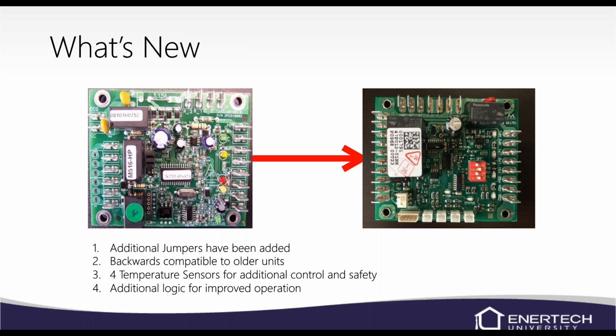So again, some additional jumpers have been added. It is backwards compatible to our older units. And we do have the little Molex connectors. You can see on the right that red dip switch box instead of those jumpers, so it stands out a little bit better. And then you can see the 4 sensor boxes on the bottom of the board. And we've just got some improved logic on the board as well.